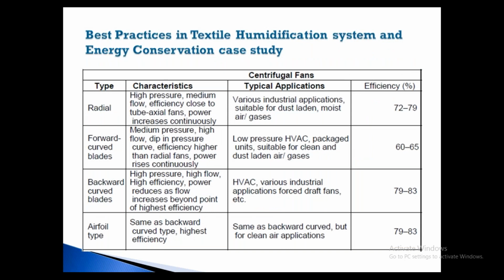So when you change the fans, not only look into the fans, you see the total system. What type of filter and filter media they are using, what the dust level is, how they are arresting the dust, and what the maintenance aspect is. As Ashok Sir was telling, what is the schedule of the maintenance? He was even telling about grease and oiling, and in the HVAC plant, what schedule they follow when they replace the filter media. This is very important. If they do not replace the filter media, it gets choked, then starvation will occur for the fan. There won't be any air for the fan, so it will go outside its good characteristic. Again, power will be more, and you will not get the output.